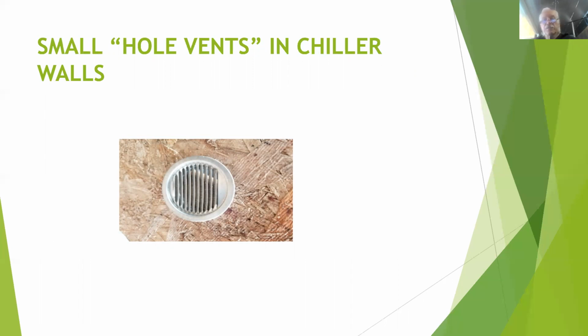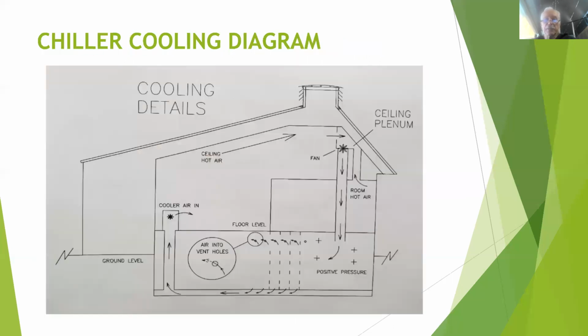To take advantage of those cool exterior walls, a series of these hole vents are put high on the inside wall between each upright stud, all along the chiller interior walls, on both the east and west walls of the chiller. Air enters these hole vents from spaces inside the chiller, travels down inside the wall cavity, and continues under the floor where it mixes with the even cooler underfloor air. This slide is a section view showing this airflow in its entirety.